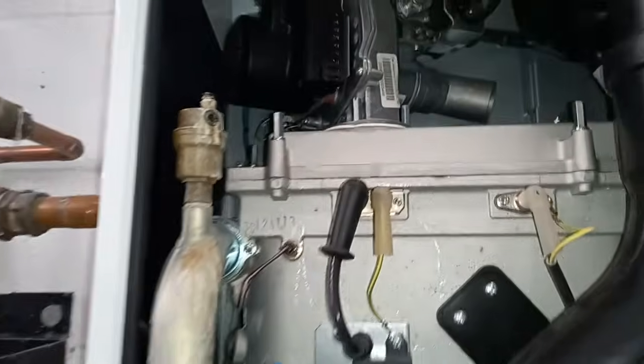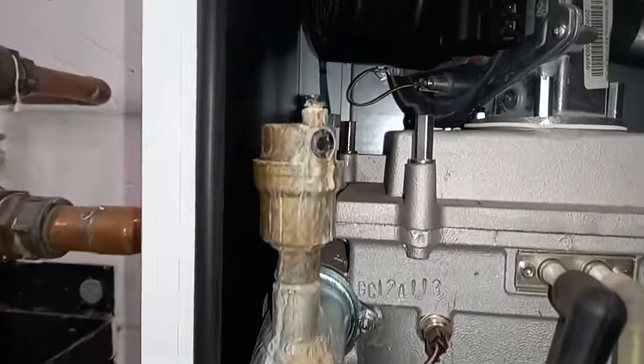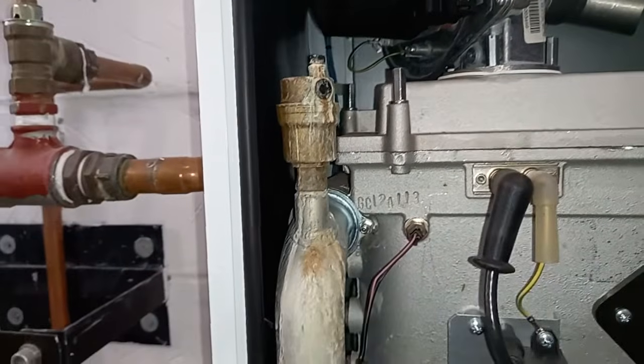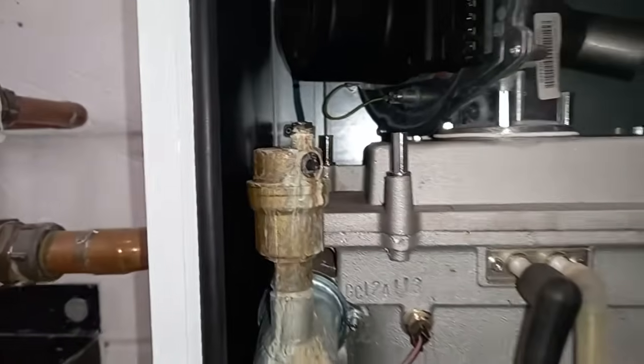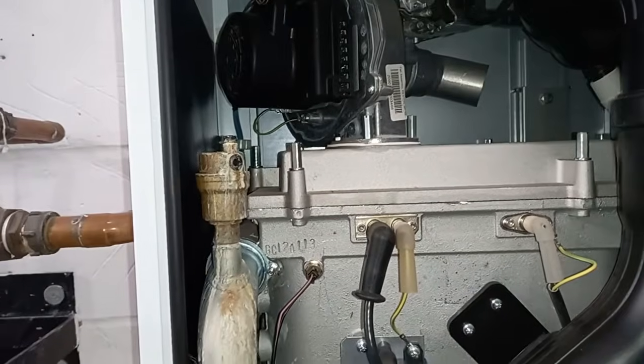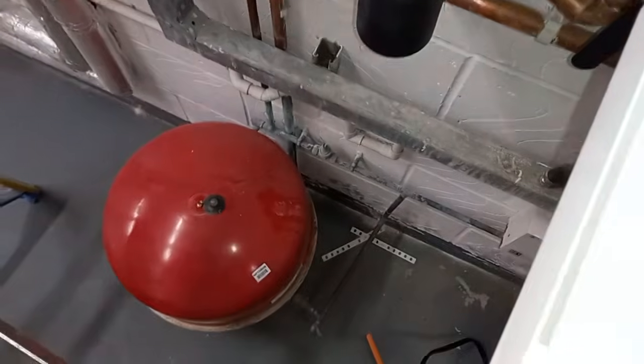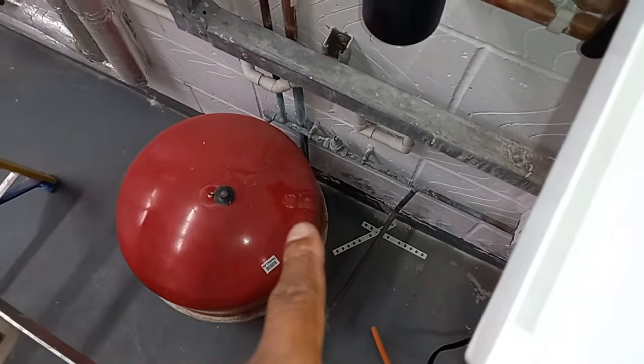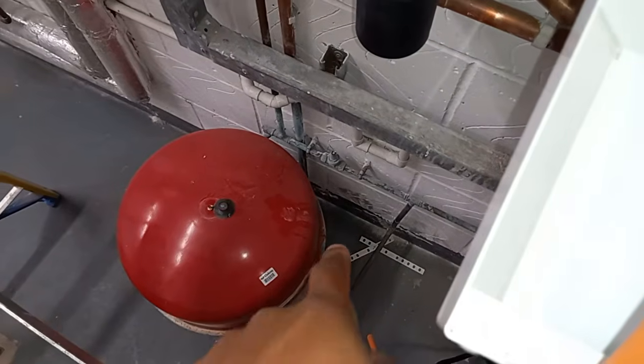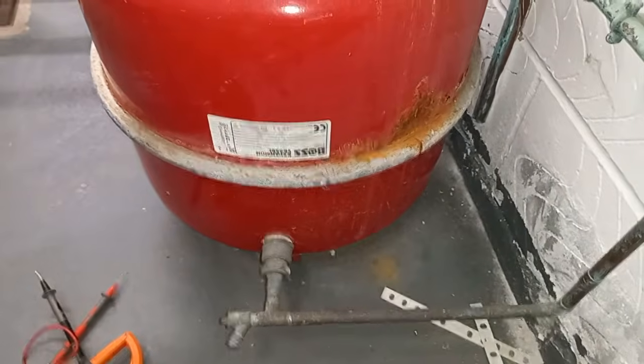So before we start, the boiler's gone off. It's just fans running to get rid of the exhaust fumes. So have a look at the condition. These AAVs on these boilers like to be in this condition a lot. I don't know why. Maybe some error, but I often see this. Other signs of dripping I saw was a little splash point there. Can you see it? That splash point on this particular unit. I think it's creating corrosion down here. So I'll mark it up. I'm not here for that, but I can see here on the unit there's a bit of corrosion. I think it's from a leak from up here.